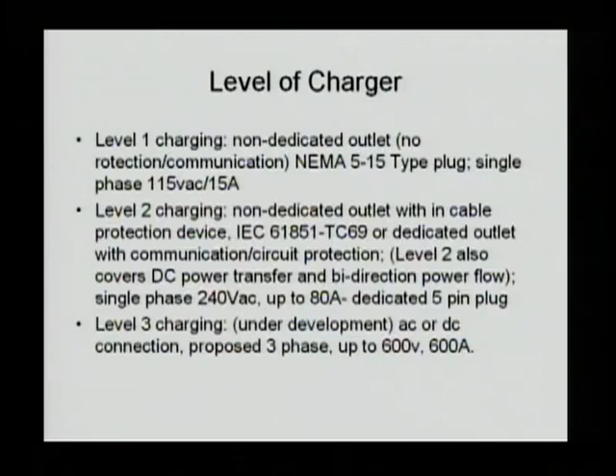In level 2 charging, it may not be a dedicated outlet, but it has to come with cable protection, or you can have a dedicated socket for charging. It also covers DC power and bidirectional power flow. That's level 2, up to 200-240 volts AC, up to 80 amps, in a dedicated 5-pin plug. Level 3 charging is more for commercial vehicles, where you can have really high current - 600 volts, 600 amps of charging current.